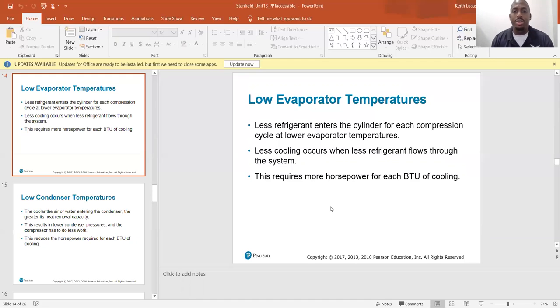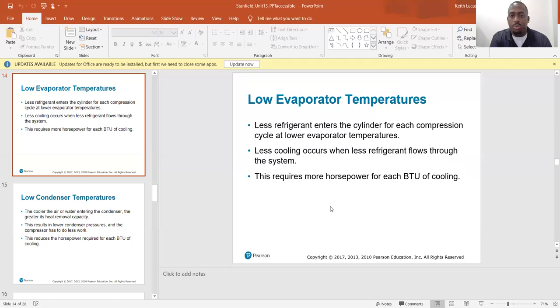Low evaporator temperatures: at lower evaporator temperatures, less refrigerant enters the cylinder for each compression cycle, so less cooling occurs when less refrigerant flows through the system. This requires more horsepower for each BTU of cooling.